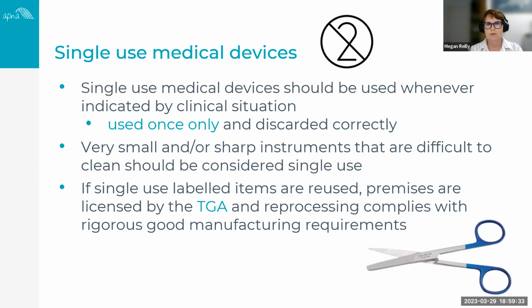So if an item is labelled single-use, it will be written in wording as single-use, or it will have the symbol that you can see on the top of the screen there. These items cannot be reused. So if you have instruments that are colour-coded with the blue, look a little bit closer because you'll find that they're single-use. You cannot reprocess these in your office-based practices unless you are licensed by the TGA and all of your reprocessing complies with the rigorous manufacturing requirements demanded by the standards. And I don't know of any office-based practice that would probably come close to actually meeting the TGA requirements for this.